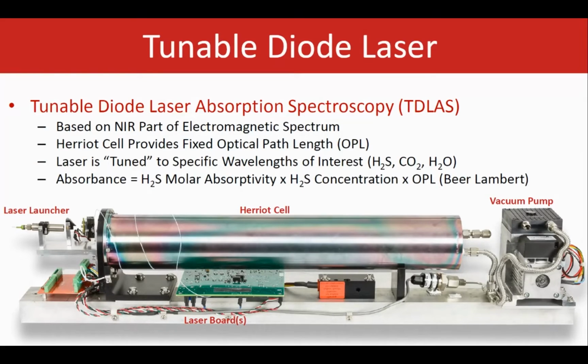Again, it is based on tunable diode laser absorption spectroscopy. It is in the near IR area of the electromagnetic spectrum. On the left side of this picture, you see the laser launcher, the cell windows, and the detector. Underneath the cell is where the laser source, the heater, the pressure transducer, as well as the vacuum pump are sitting. Now, in order to make the measurement, the specific wavelength of the light emitted by the laser is controlled by adjusting the current and the temperature of the laser emitter.